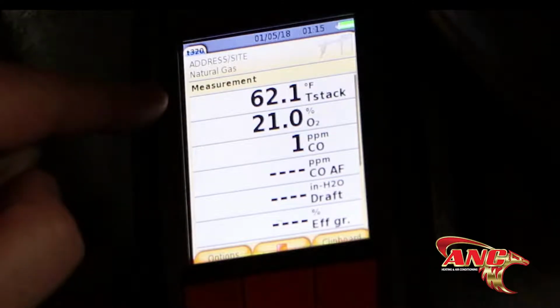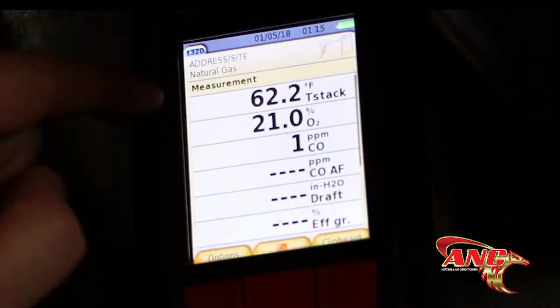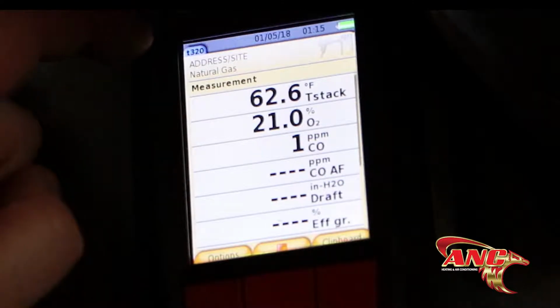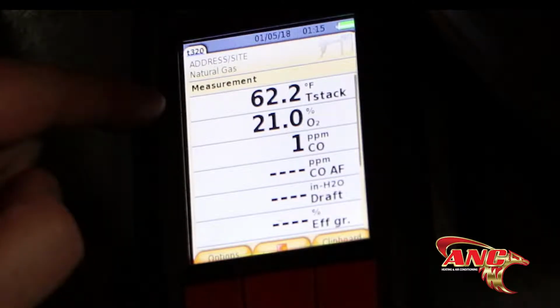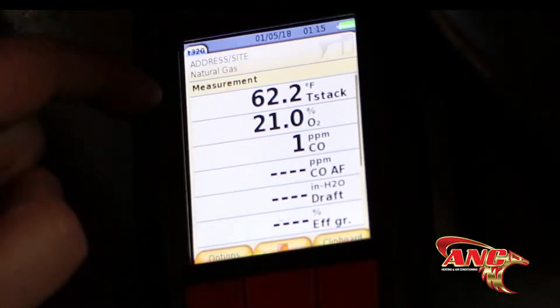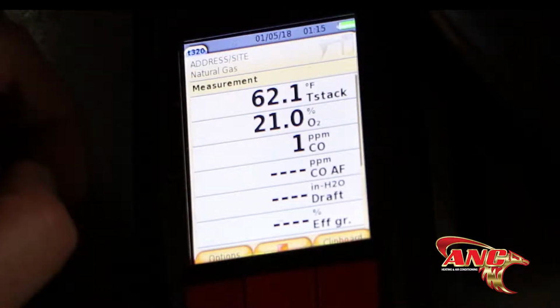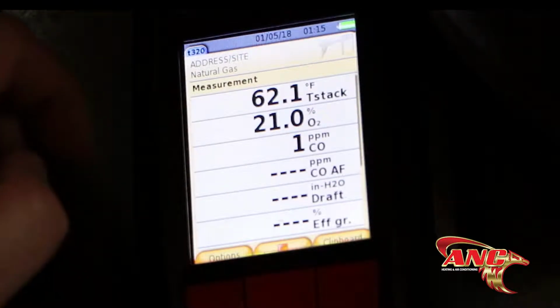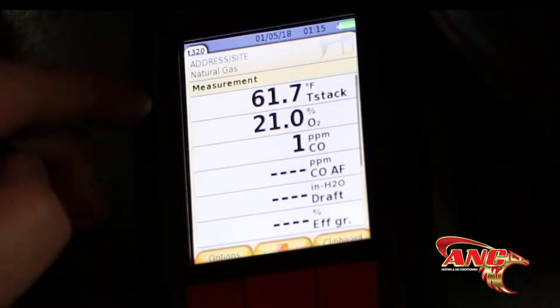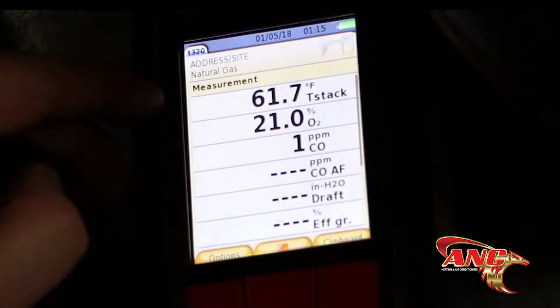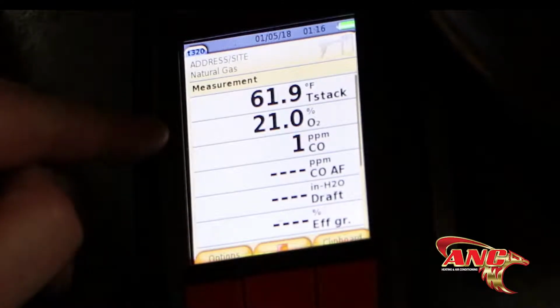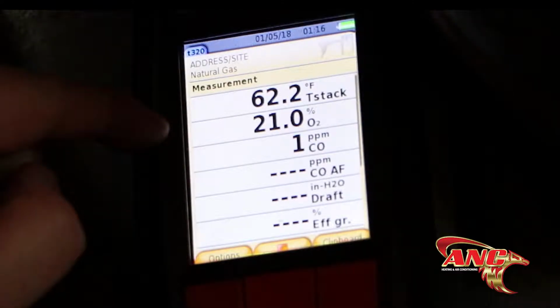If it gets over that, there may be some issues with a secondary drain clogging, or just the drains in general clogging. What we don't want to see is very high temperatures, somewhere in the 130 to 150 range. If that's the case, then we're in a dangerous situation. PVC is not rated to vent that high of temperatures, and go from there. The second number here is going to be an oxygen percentage.